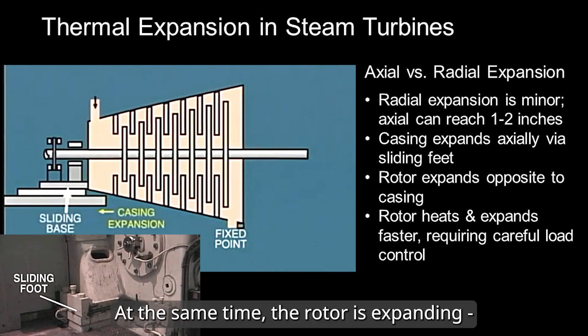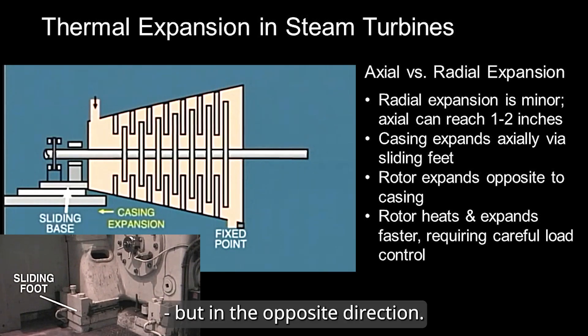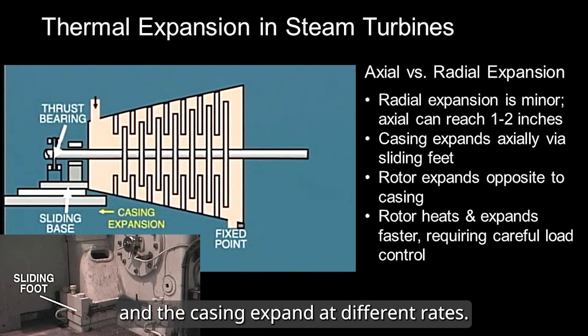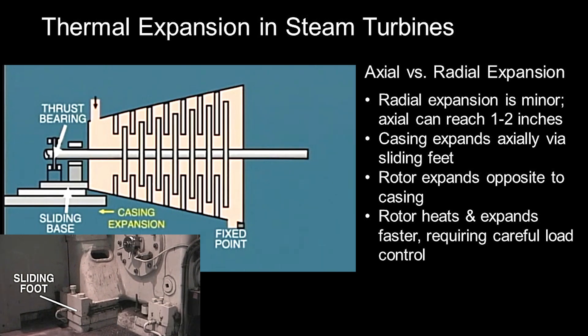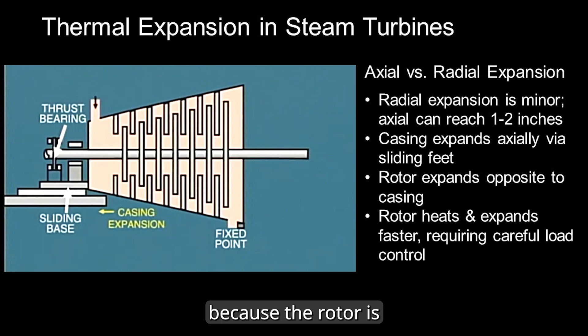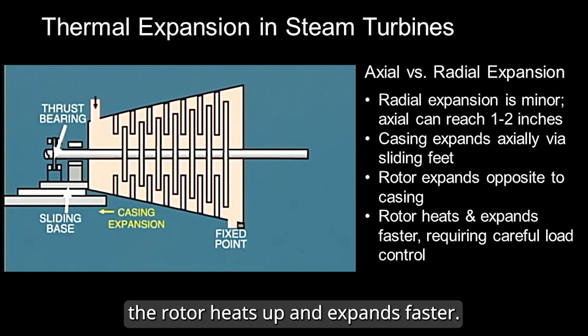At the same time, the rotor is expanding, but in the opposite direction. Since the thrust bearing holds the high pressure end, the rotor and the casing expand at different rates. Because the rotor is lighter than the casing, the rotor heats up and expands faster.